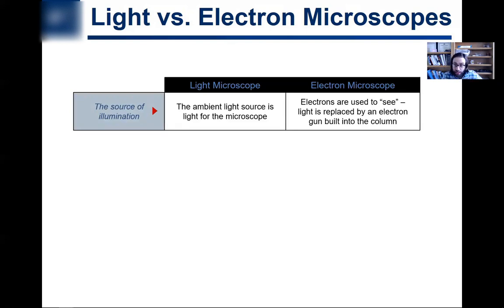In an electron microscope, you are using electrons to see, but you can't see electrons so you have to transmit those electrons somehow into an image that you can see with your eyes. Usually this is done through some sort of luminescent plate that when electrons hit this plate you will see it. There's different ways - depends on whether or not it's SEM or TEM. You have an electron gun and the electron gun is what is generating the electrons that are used to do the imaging.